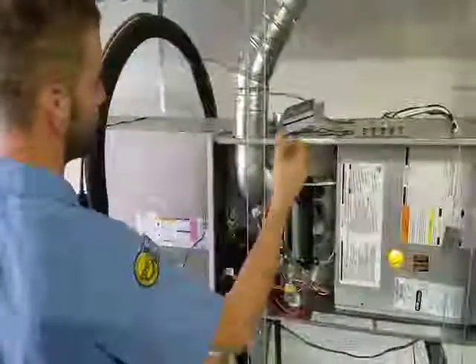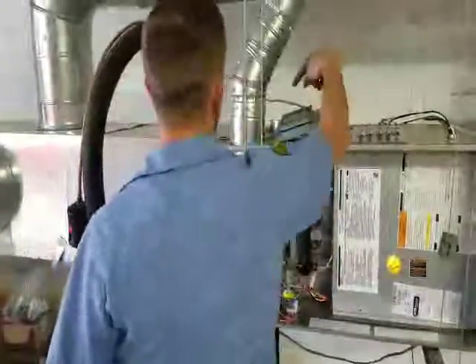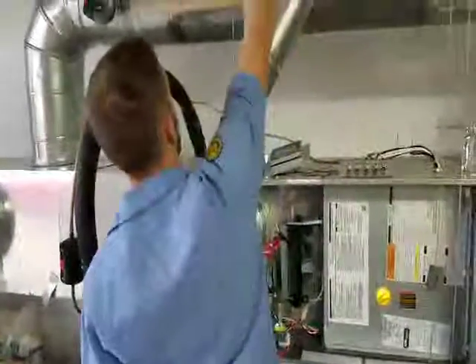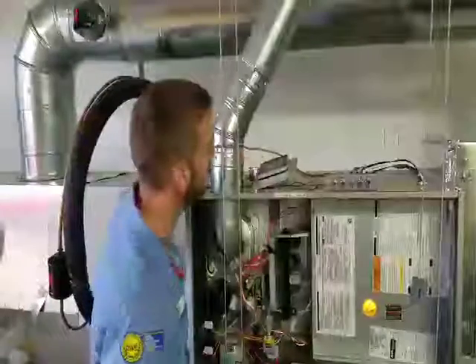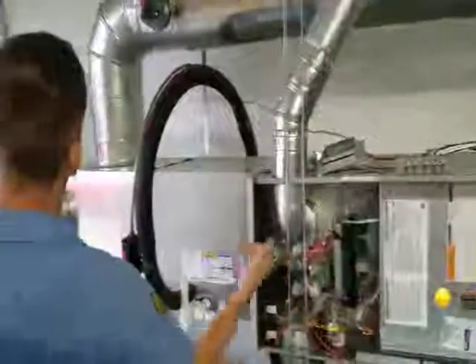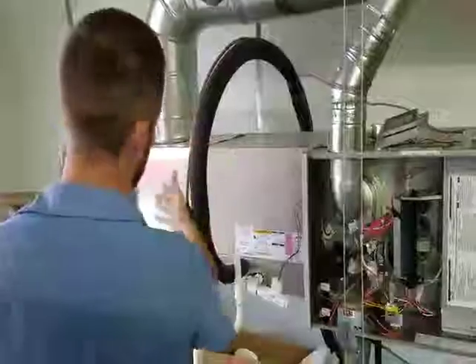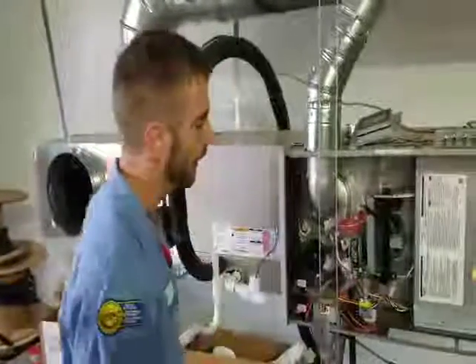Now when that gas fires through, it comes through your heat exchanger, comes back out, and this inducer motor is what draws that carbon monoxide out through your roof. Now if there's a crack anywhere back here in your heat exchanger, it's going to leak right into your main airstream and dump into your home.